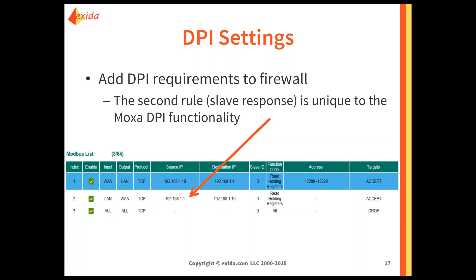The second line is unique to the Moxa configuration. The Moxa requires you to put in a rule to allow the slave response to come back from the device. So in this case it's LAN to WAN — the reverse. It's coming from .1, which is my PLC, to .10, which is my HMI, covering all slave IDs and all holding registers. What this does is: for any read-holding register request that goes out to this device, the slave response is permitted to come back. Line three: all other function codes trying to be passed to all devices through this firewall are going to be dropped and logged. Again, that's firewall best practice.